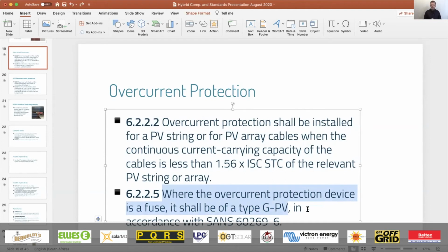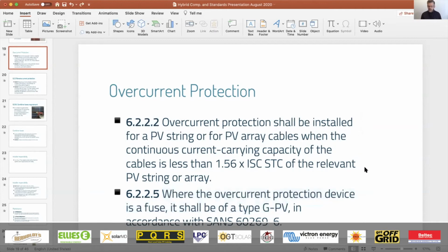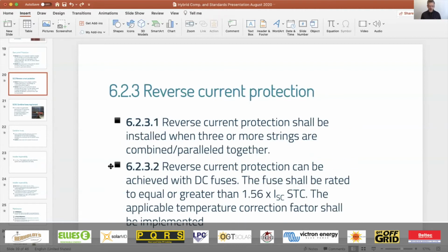So guys, the GPV, extremely important because a GPV fuse can handle its full rated current for quite a few hours. So you can't use an AC fuse in a DC environment. And when you do solar installations, just make sure that the fuses you use are GPV rated fuses. That, of course, is also highlighted in the standard. Reverse current protection.